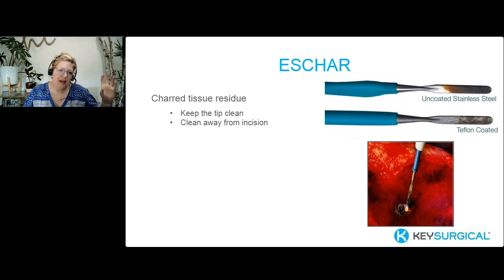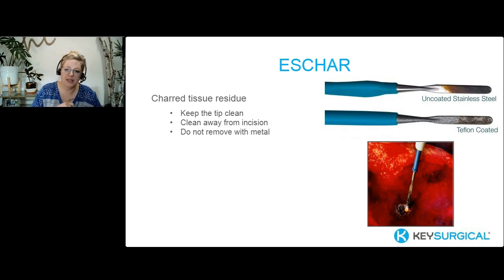Do not remove it with metal. That goes right back to our insulation conversation, as well as our instrument integrity. Not using any metal to clean. That eschar is sticky. It's like cleaning burnt chicken off of a pan, or caramel, right? It's actually called tissue caramelization for a reason. Very sticky, very challenging to remove, but we don't want to remove it with metal because we can damage insulation and instruments. We should be monitoring our power settings. Eschar actually impedes electrical current. So if you have a surgeon who says, turn up, I need more power, or they're consistently asking, or they're using more than they usually do for that procedure, take a look at your instrument, kind of pause for safety in that instance, because we know that increased power settings are associated with increased patient risks.